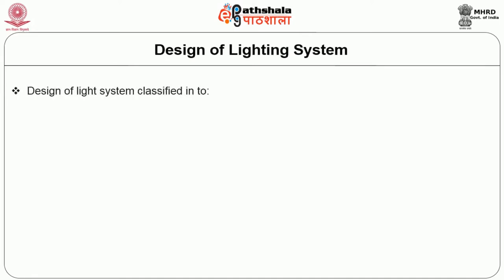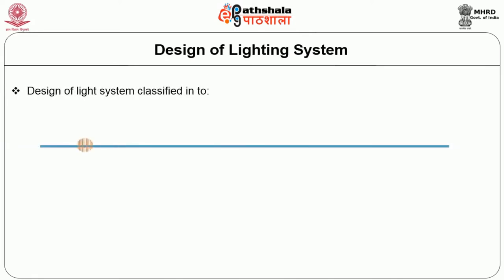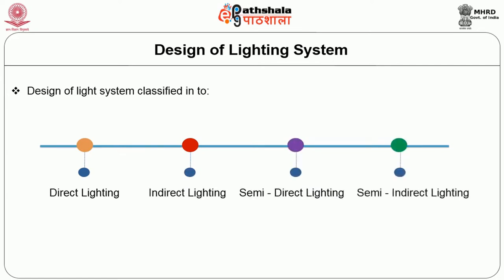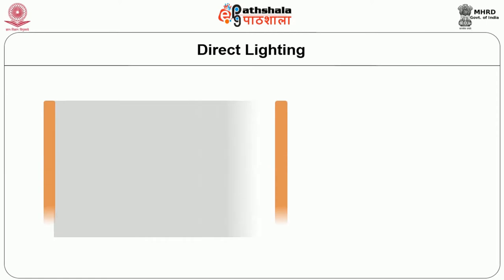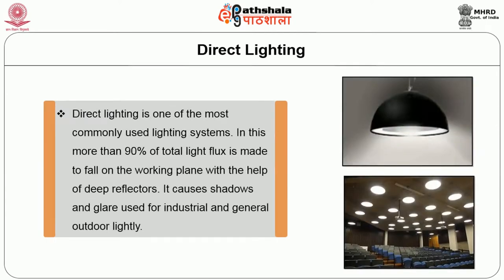Design of the lighting system: lighting systems are classified into direct lighting, indirect lighting, semi-direct lighting, and semi-indirect lighting. Direct lighting is one of the most commonly used lighting systems. In this, more than 90% of total light flux is made to fall on the working plane with the help of deep reflectors. It causes shadows and glare, and is used for industrial and general outdoor lighting.